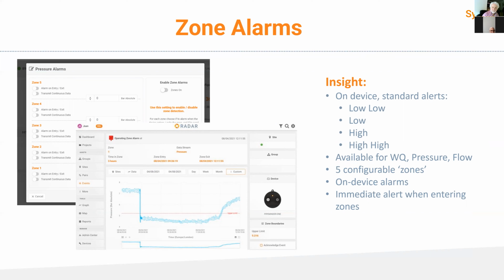The basic concept with a zone alarm is that you've got 4 configurable thresholds, which define 5 zones. And when the signal, for example pressure, enters each of those zones, you can decide what to do. So you could define zone 3 as your normal operation zone, and we'll do nothing. We're expecting the pressure to be within those upper and lower bounds. You could then define some higher and lower zones where perhaps when you enter that zone, we'll send an alarm, or you can send continuous data.